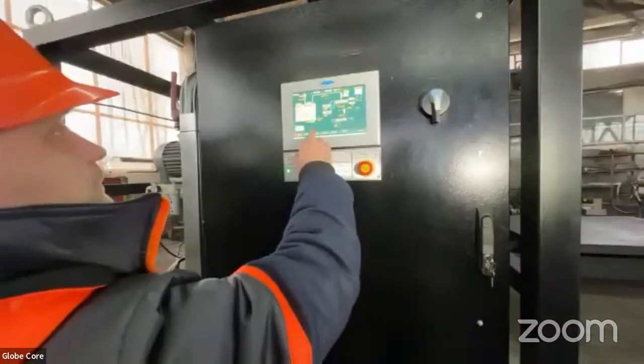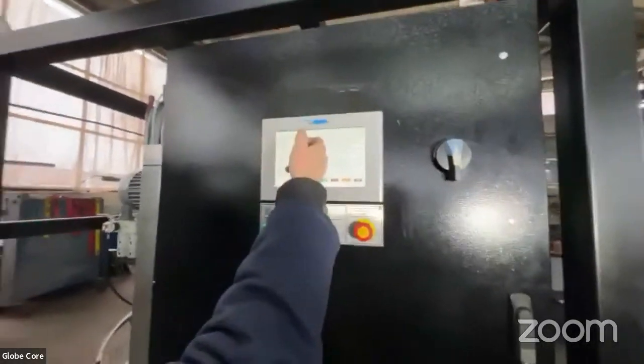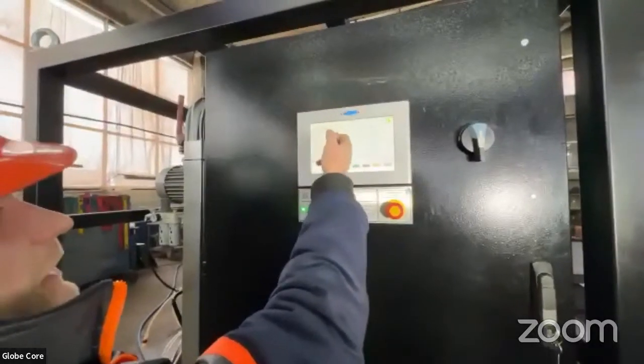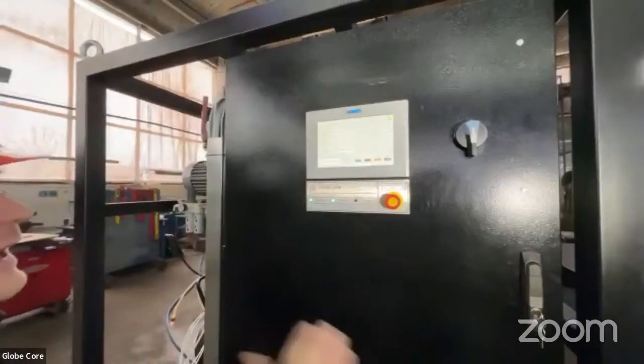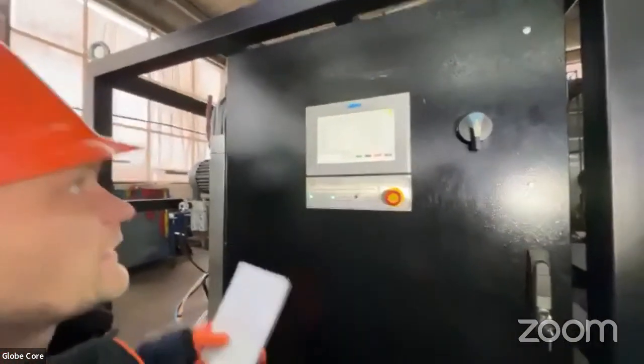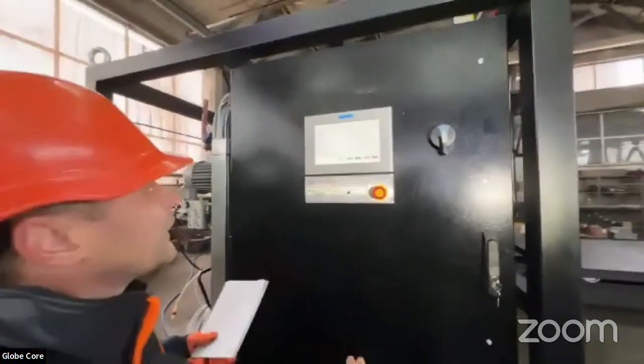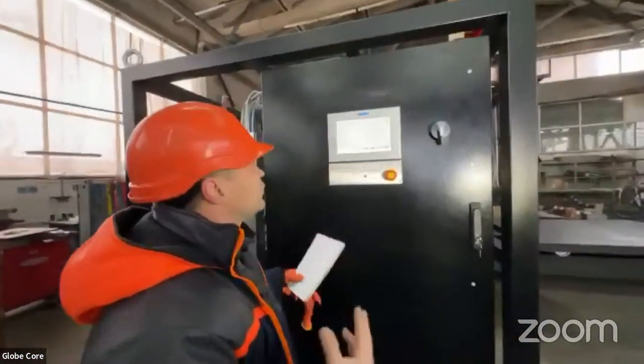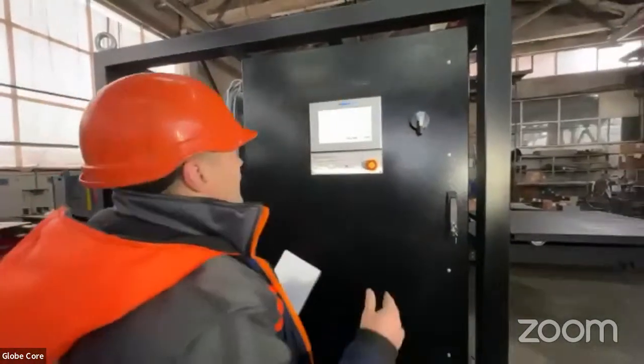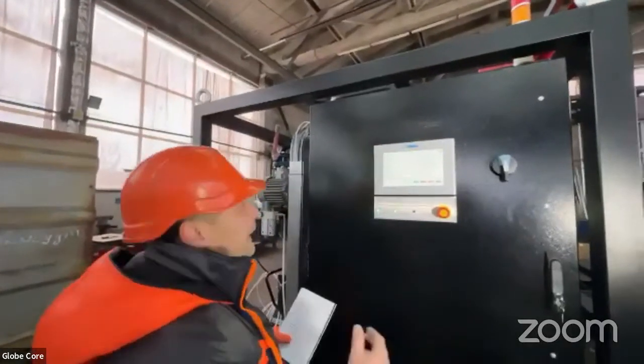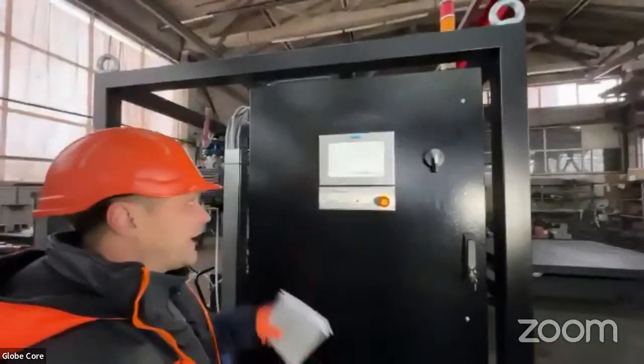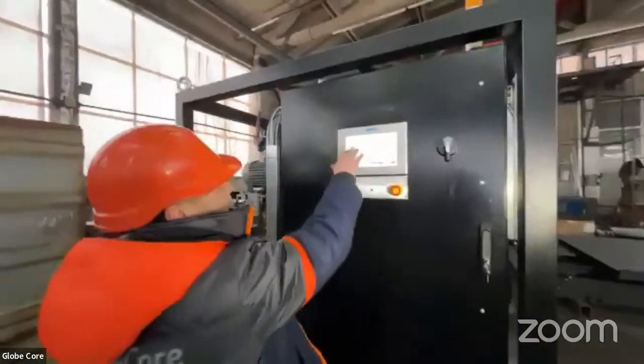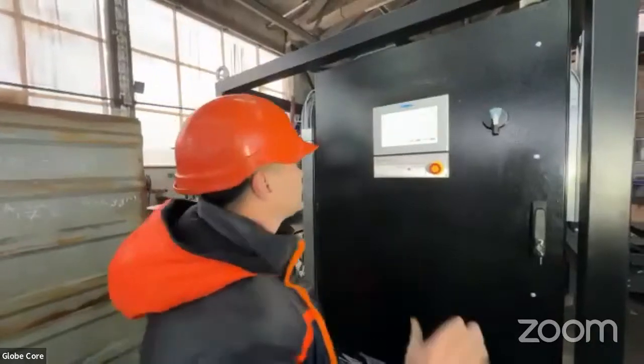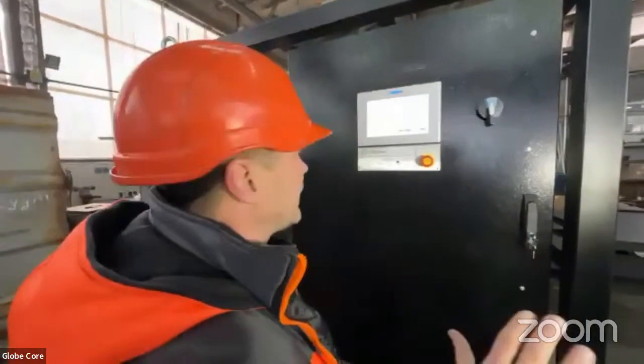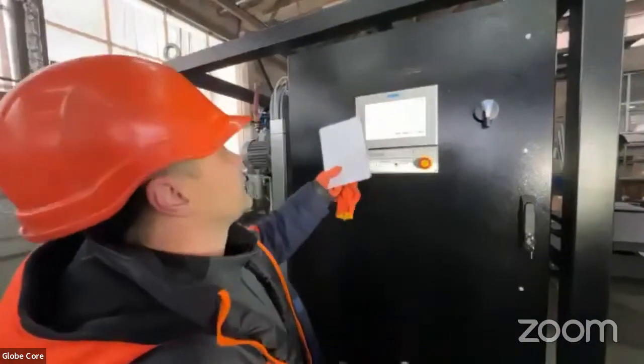The automatic mode is set in here. So at every step, we set the value of vacuum and temperature to be reached, then the time when the system is keeping the parameter, and when the moisture is extracted. After each step, we remove the extracted media enriched with water by opening the air inlet valve and by turning on the extracting fan. And after that, the system performs the next step. The next step is at the highest temperature and the highest value of the vacuum. Altogether, the system is supposed to perform 6 automatic steps with different time, temperature, and vacuum value.